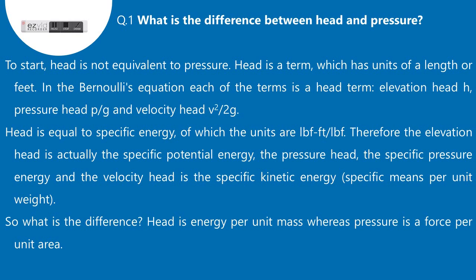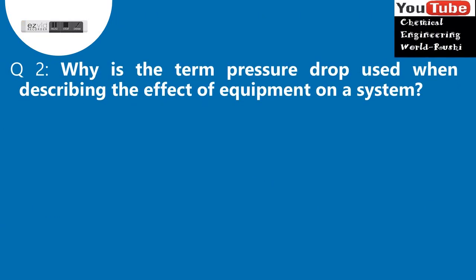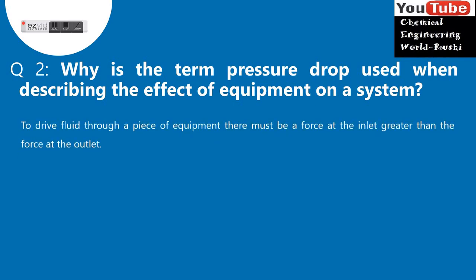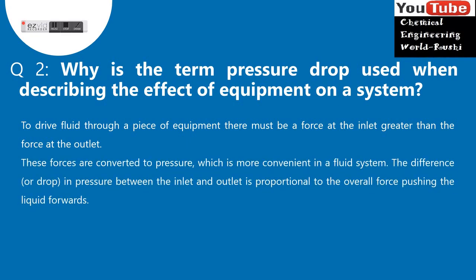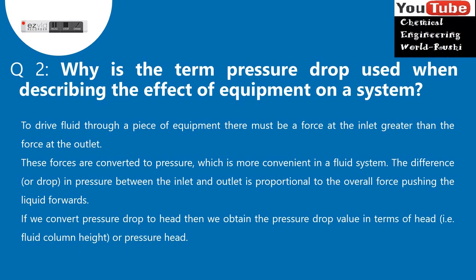Question 2: Why is the term pressure drop used when describing the effect of equipment on a system? To drive fluid through a piece of equipment, there must be a force at the inlet greater than the force at the outlet. These forces are converted to pressure, which is more convenient in a fluid system. The difference, or drop, in pressure between the inlet and outlet is proportional to the overall force pushing the liquid forwards. If we convert pressure drop to head, we obtain the pressure drop value in terms of head, that is fluid column height, or pressure head.